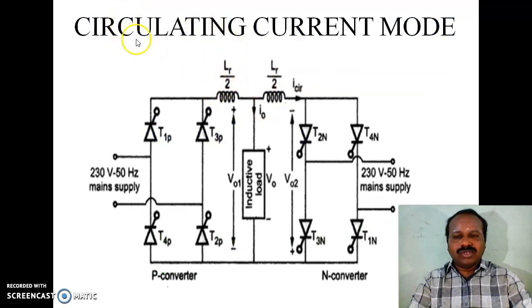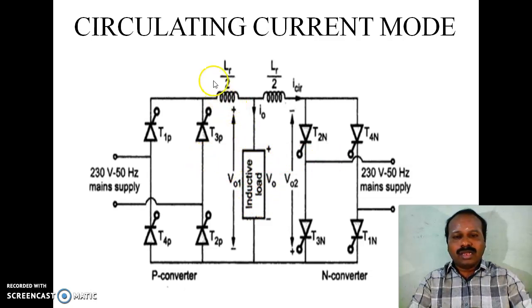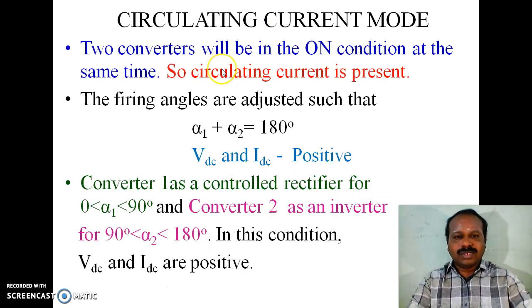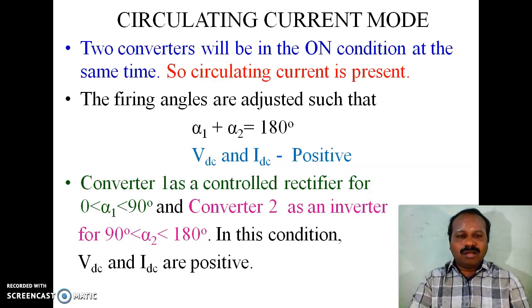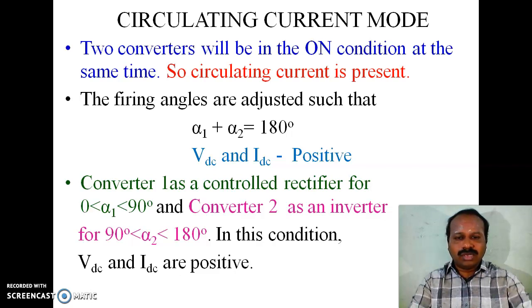This is the complete diagram showing circulating current mode. Converter 1 (positive converter) and Converter 2 (negative converter) are connected back-to-back to the common load. Lr/2 inductors on both sides are used to limit the circulating current — this is known as a reactor. In circulating current mode, both converters are in the on condition at the same time, so circulating current is present. The firing angles are adjusted such that alpha 1 plus alpha 2 equals 180°.